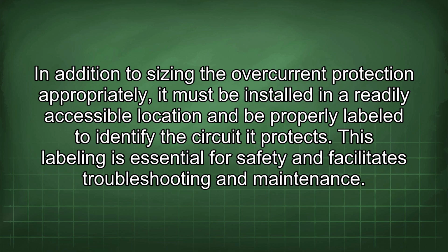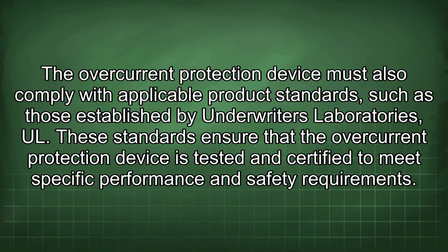In addition to sizing the overcurrent protection appropriately, it must be installed in a readily accessible location and be properly labeled to identify the circuit it protects. This labeling is essential for safety and facilitates troubleshooting and maintenance. The overcurrent protection device must also comply with applicable product standards such as those established by Underwriters Laboratories (UL). These standards ensure that the overcurrent protection device is tested and certified to meet specific performance and safety requirements.